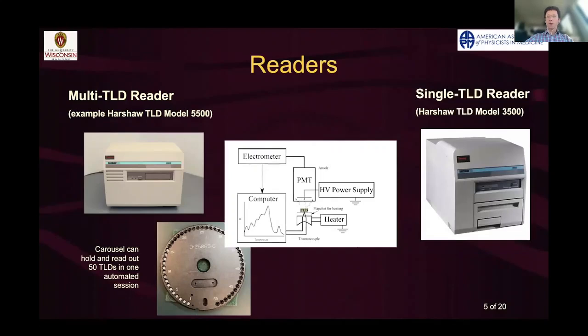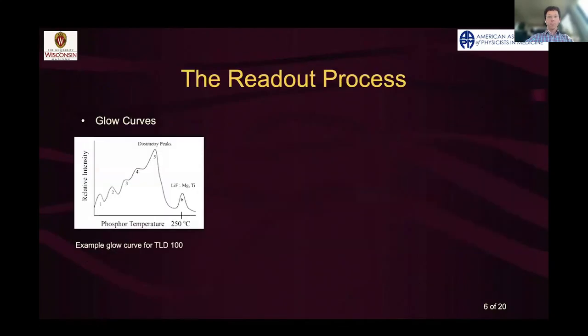There's also a single TLD reader, which is what a lot of hospitals have. Some older ones are around still. This one's called a Model 3500, where the TLD is placed on a planchette or a little hot plate, and that hot plate is heated up and a photomultiplier tube reads out the light.